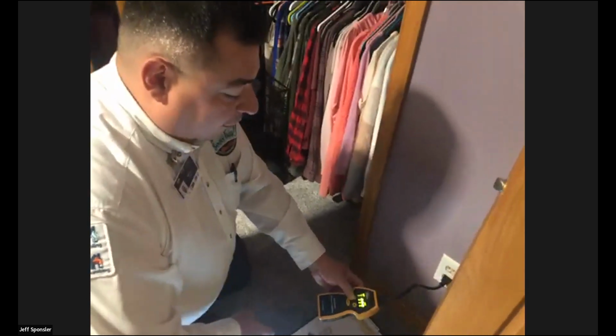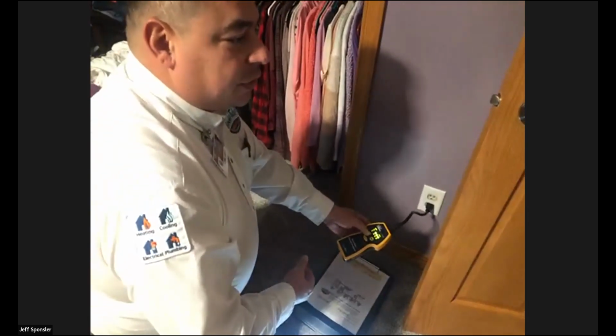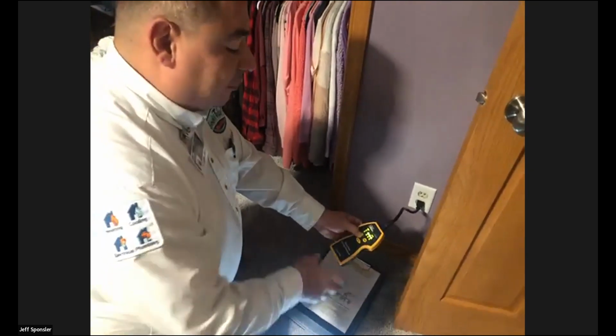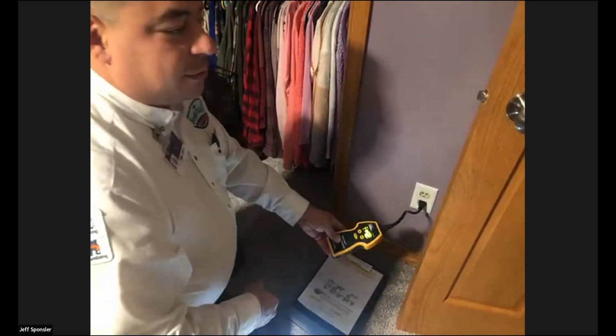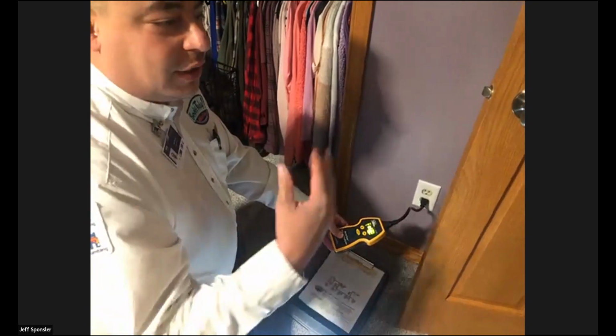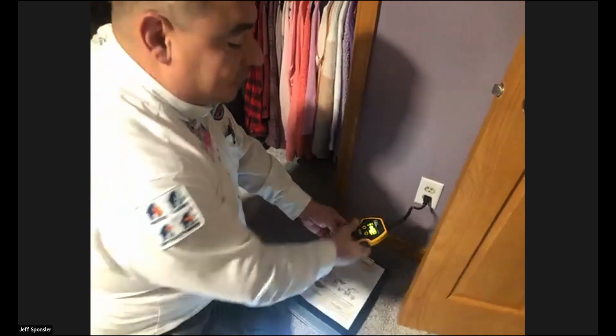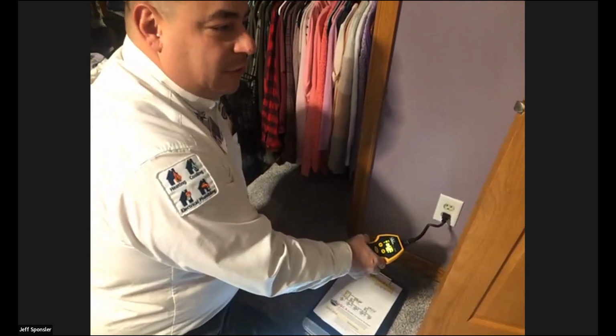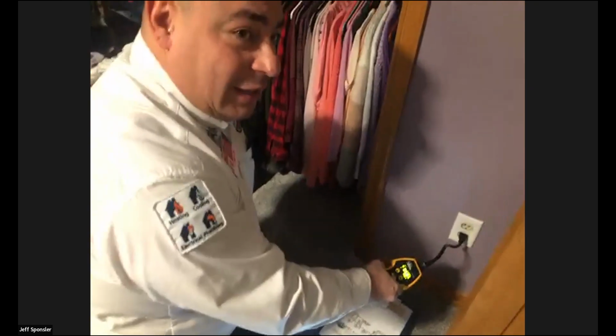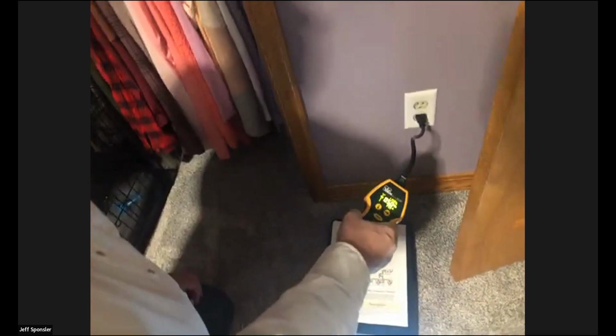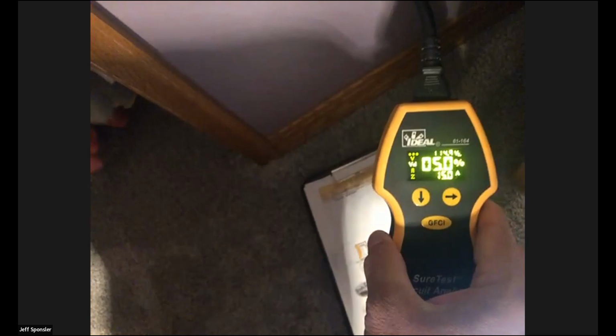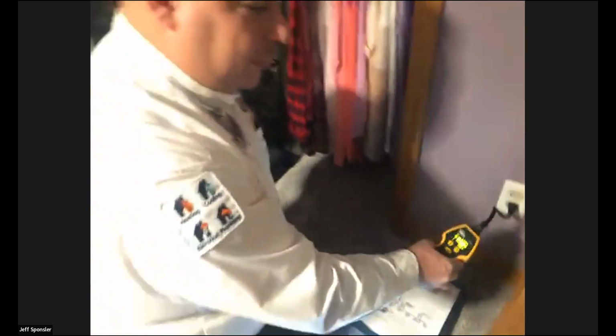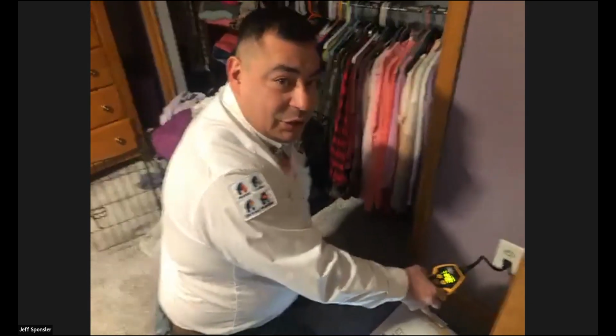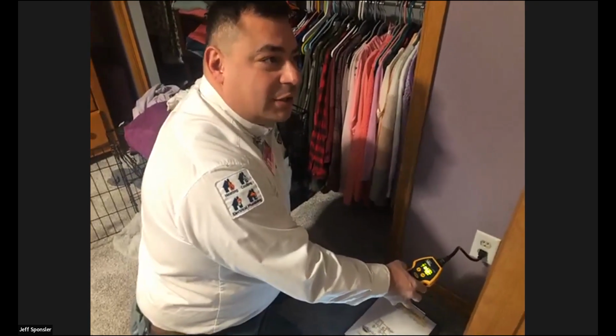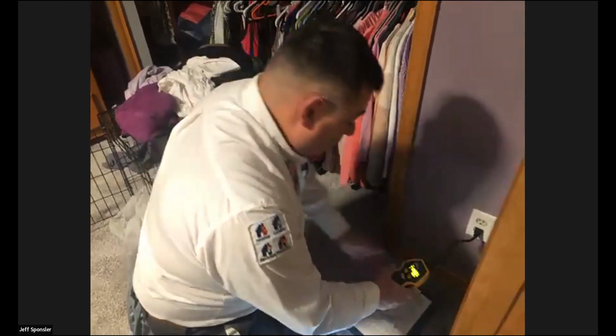After I get a couple readings, usually if I find something with a low percentage and a high percentage voltage drop, that's when I input into Slack. I take photos of the panel, one inside, one outside, to update right away, along with the voltage drop information. I try to do that within the first half hour if possible, so the office can track what I'm doing and let me know via Slack if they have any suggestions.